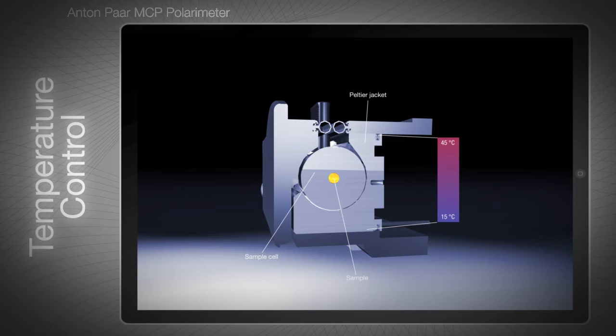You do not have to worry about operating or calibrating an external water bath. The sample cell is in ideal thermal contact with the Peltier jacket, surrounding 50% of its surface. When you select a temperature below ambient in the software, the heat from the cell and sample is extracted from several directions and dissipated by fans. This works fast and avoids errors from thermal gradients in the cell.